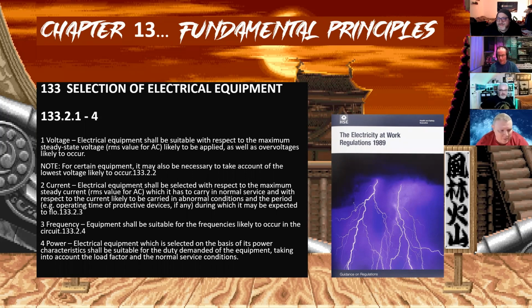Frequency: equipment shall be suitable for the frequencies likely to occur in the circuit. Power: electrical equipment which is selected on the basis of its power characteristics shall be suitable for the duty demanded of the equipment, taking into account the load factor and the normal service conditions. Lots of shalls again, basically all the fundamental electrical characteristics.